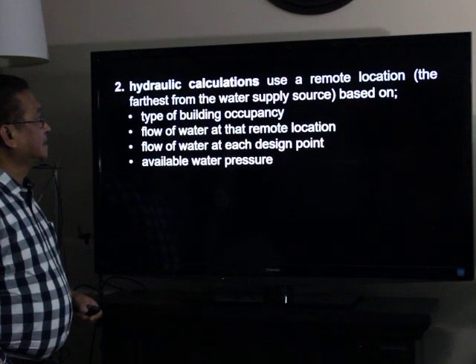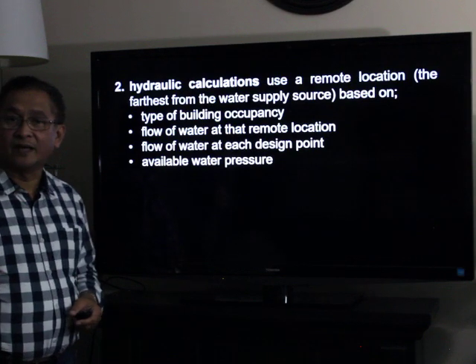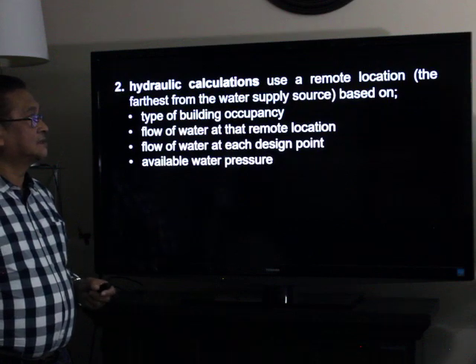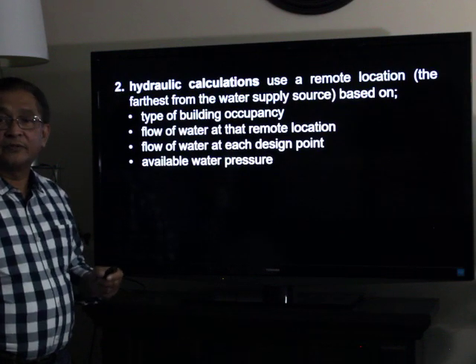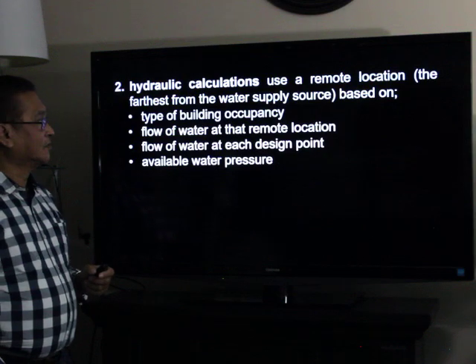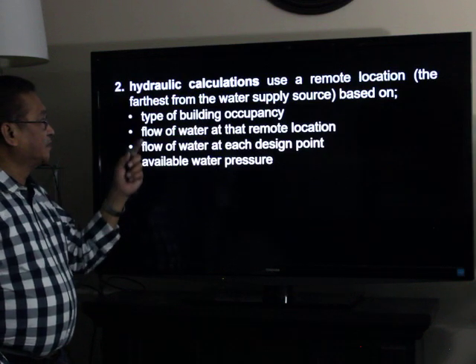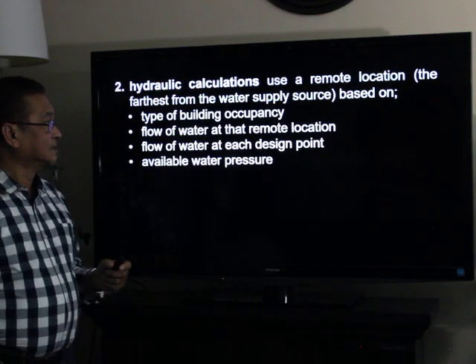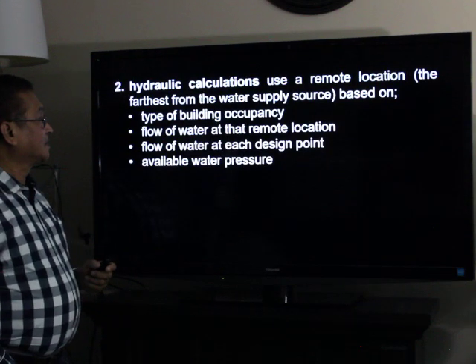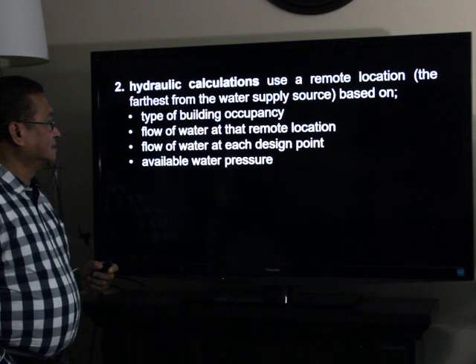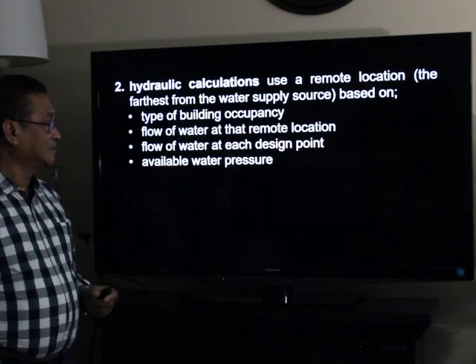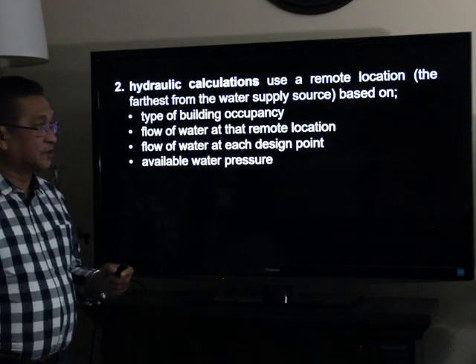The second method is the use of hydraulic calculations. Hydraulic calculations are based on a remote location — the farthest from the water supply source — the type of building occupancy, the flow of water at that remote location, the flow of water at each design point, and the available water pressure.